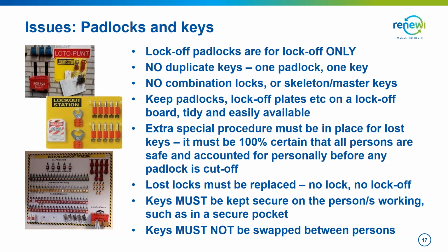Padlocks and keys. Let's be clear on this. Lock-off padlocks are for lock-off only. They should not be borrowed for security reasons or any other use. They are dedicated to lock-off. There should be no duplicate keys whatsoever. 1 padlock, 1 key. Any duplicates should either be kept secure or better, actually just destroy them. Padlocks are cheap, yeah, so no problem there. Obviously no combination locks or skeleton or master keys.